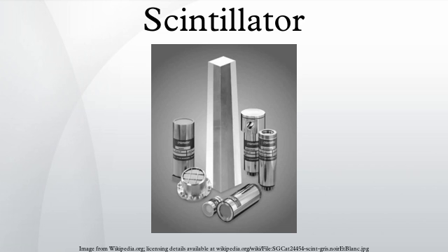A disadvantage of some inorganic crystals, for example NaI, is their hygroscopicity, a property which requires them to be housed in an airtight enclosure to protect them from moisture. CsI(Tl) and BaF2 are only slightly hygroscopic and do not usually need protection. CsF, NaI(Tl), LaCl3(Ce), LaBr3(Ce) are hygroscopic, while BGO, CaF2(Eu), LYSO, and YAG(Ce) are not.